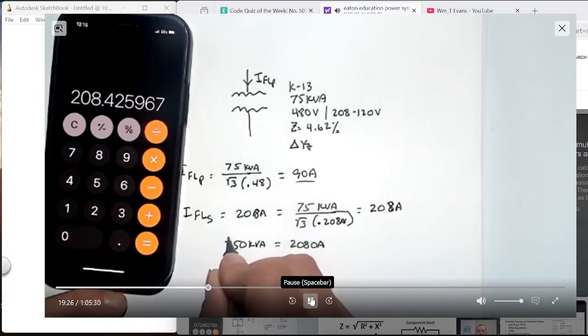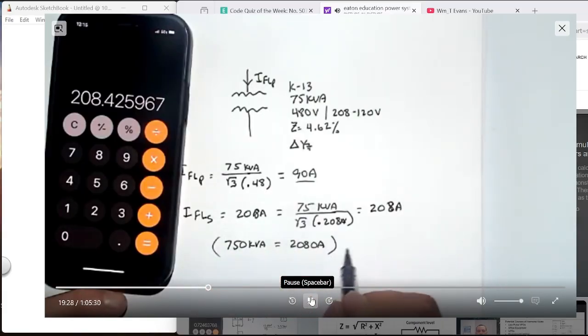And again, that's just a side note, a rule of thumb, something to remember in the back of your mind. And as I said on the previous page, what if it was 300 kVA? Well, it's 4 times this number. So an easy calculation to remember. So that's full load amps primary to secondary.